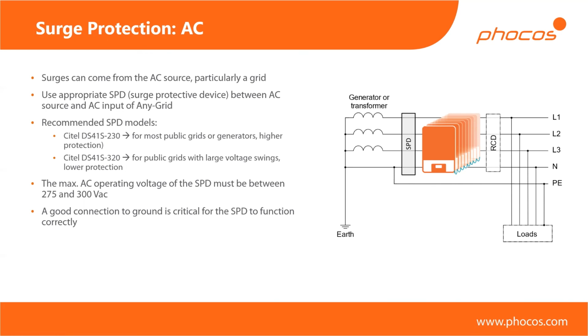Again, this doesn't cost much, maybe in the realm of $20 to $50. This is a very standard component, the surge protector for the grid side. It is for when there's lightning or anything in your area and a high voltage peak comes in through the grid, or if you have an AC generator, for example. This surge protective device will cancel that peak. Our recommendation: we have two models listed here for various scenarios, depending on the quality of the grid.